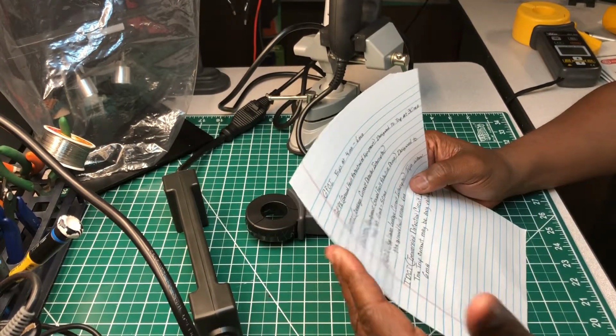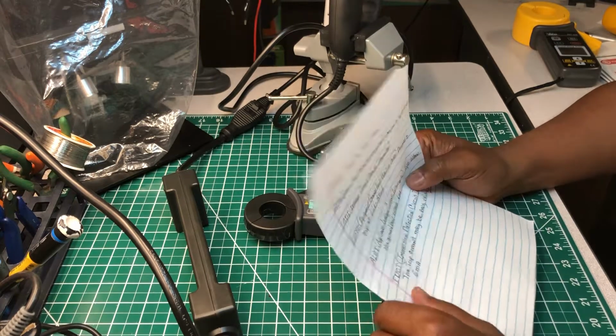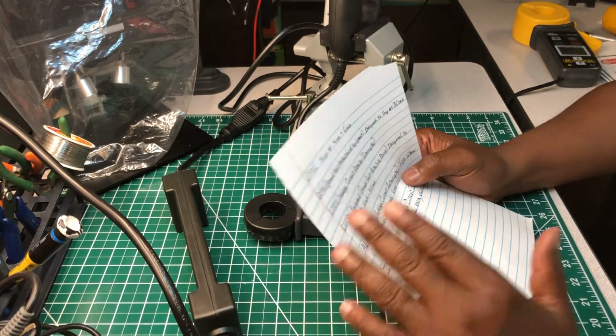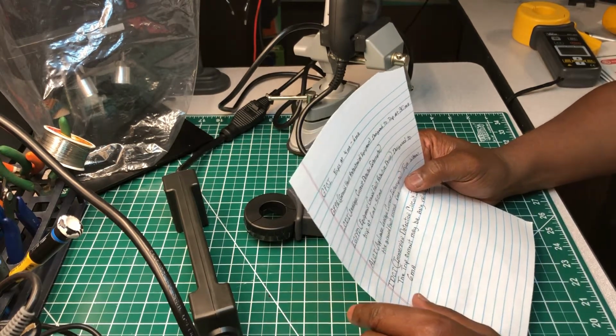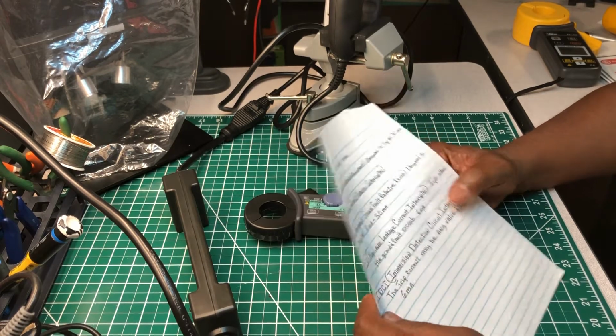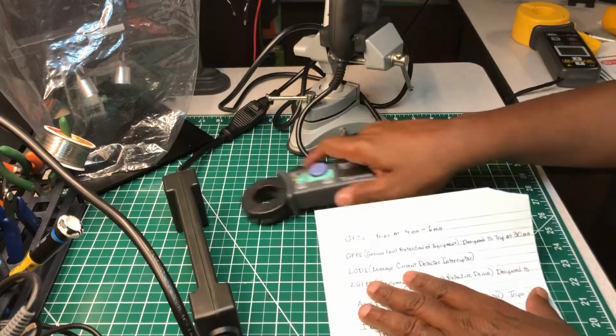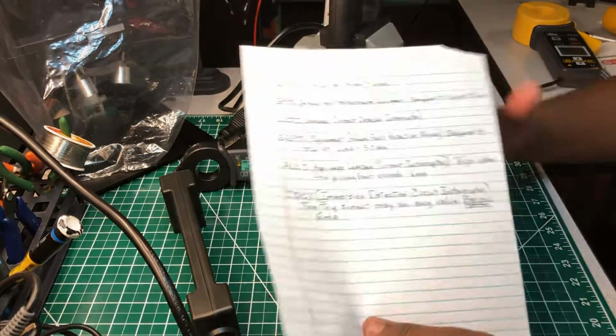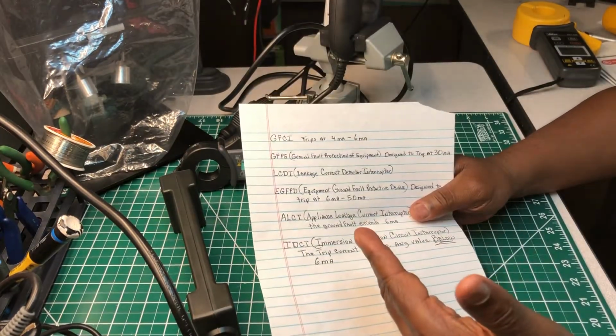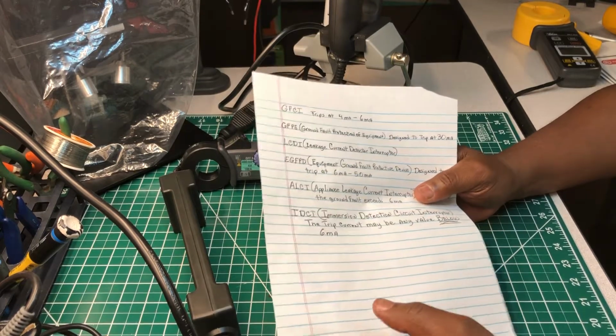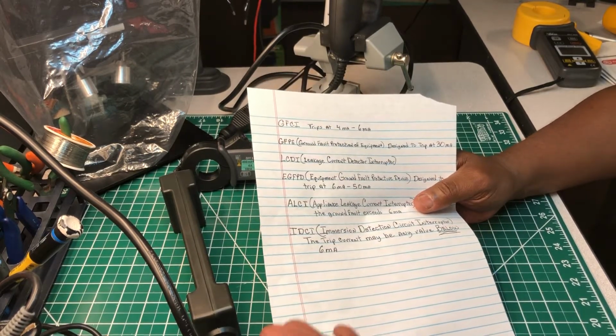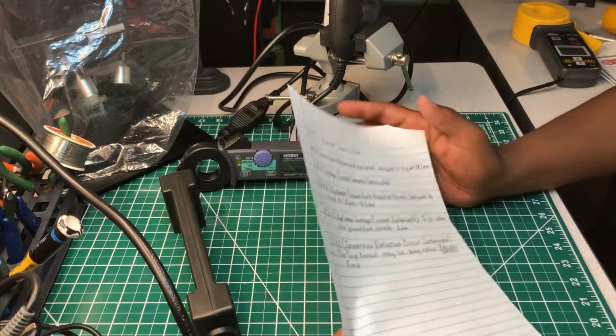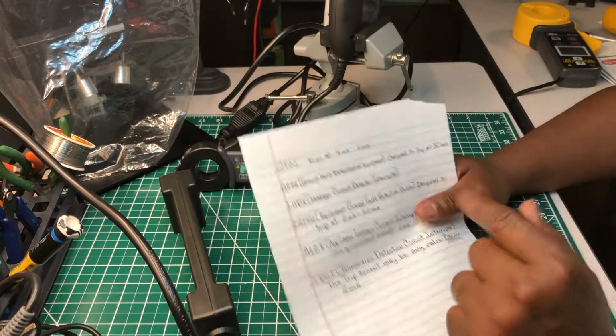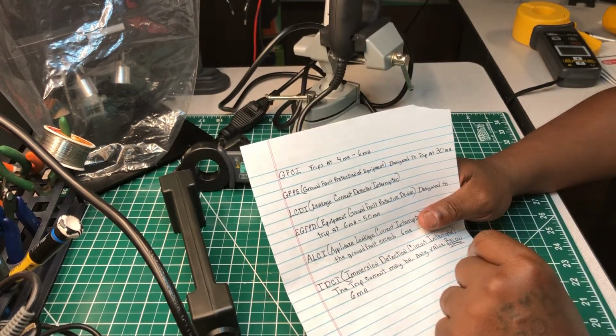Now you may be working on a circuit that has a GFCI, and it may be tripping intermittently all the time, and you don't know what's wrong with it. The majority of the time, if you didn't know anything about this instrument, you would figure it must be just a bad GFCI. But not all the time. You got me? Not all the time. That's where leakage current testing comes in. The appliance that you plug into that outlet may cause that problem.